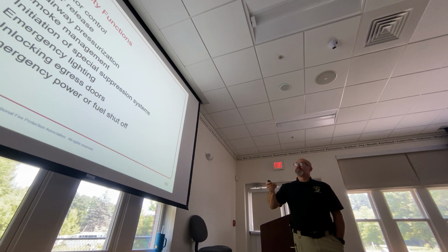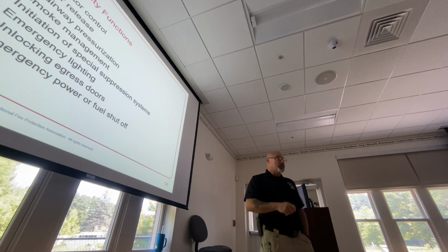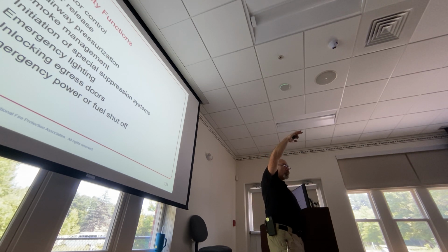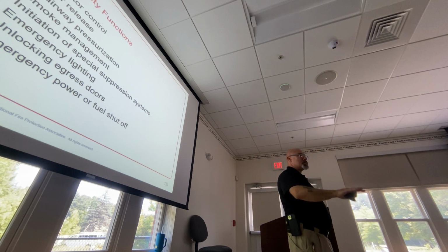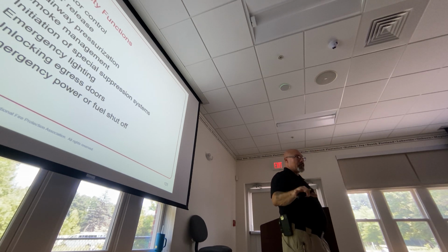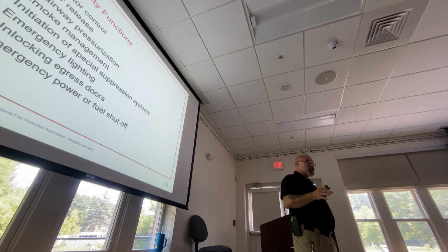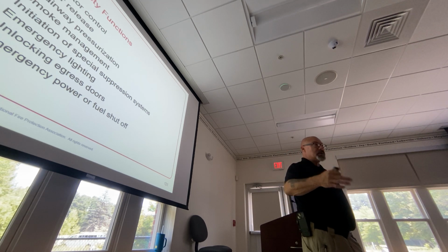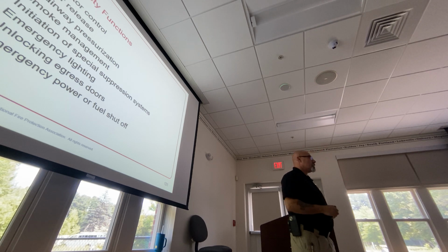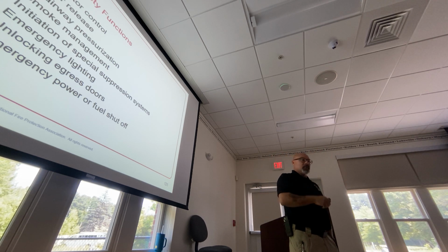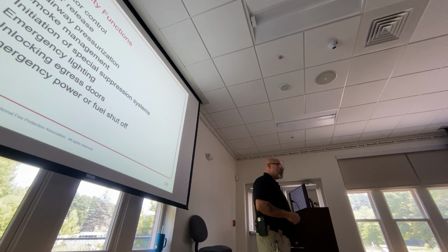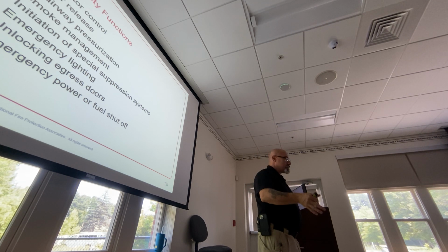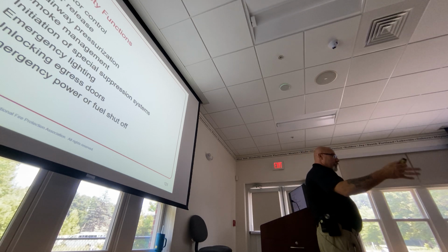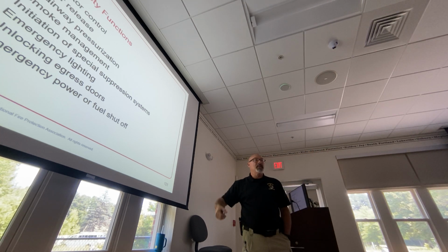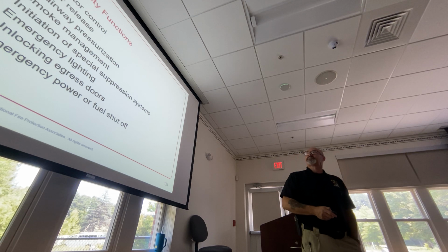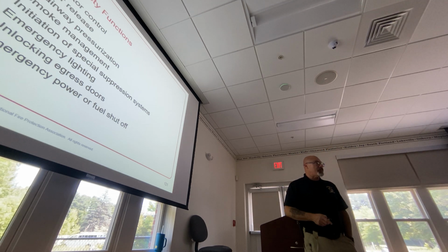Okay, elevators. Typically, if the fire alarm goes off, the elevator goes into a recall mode, where it goes back to a specific floor designated by the fire department. Because as fire chiefs, you want to be able to send your crews in and potentially utilize that elevator. Elevators generally are not a required means of egress, so people don't get in them. It's going to go down to that specific floor for the fire department to use. They stick their key in, then they can use it. All controlled or all part of a fire alarm system.